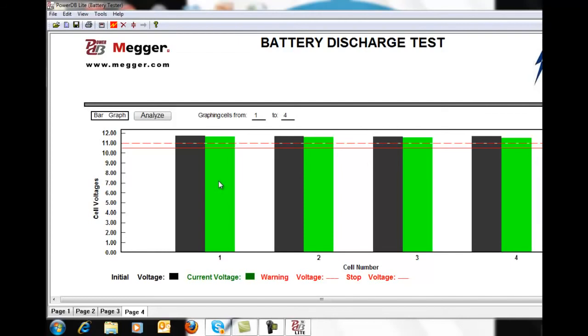So what I will see here is the green bar come down and hit the warning, and the Torkel will then indicate a warning to us. As the green bar comes down to the cutoff line, the Torkel will then end the test when all cells and jars have reached the cutoff value. The value of monitoring each individual cell allows me to see if one of the cells in the battery string is possibly defective and is decaying at a much quicker rate than the remaining cells.